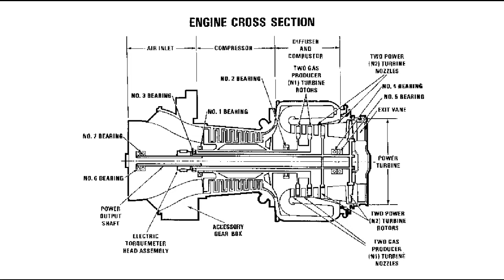As we consider higher temperature gas turbines, their energy efficiency is higher. So in the end, the materials available to produce blades and surrounding parts of the gas turbine that withstand high temperatures decide how much efficiency of a gas turbine may be achieved.